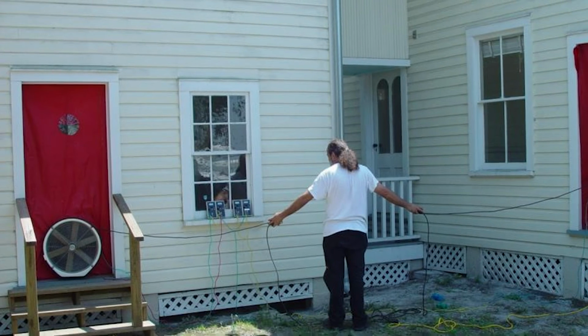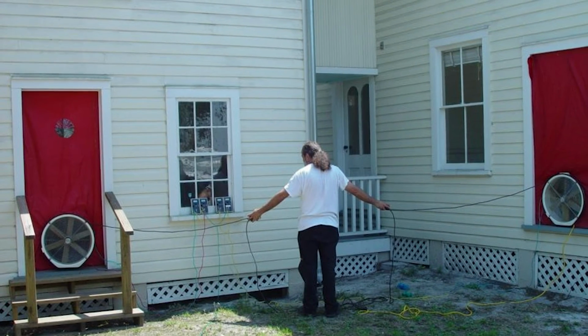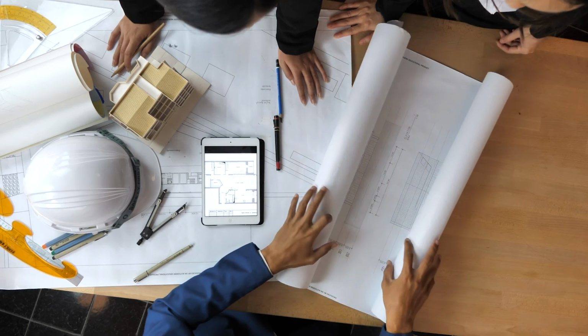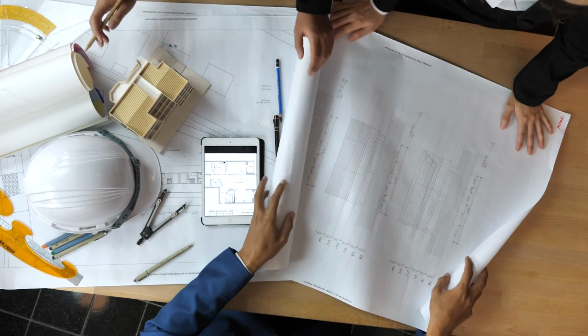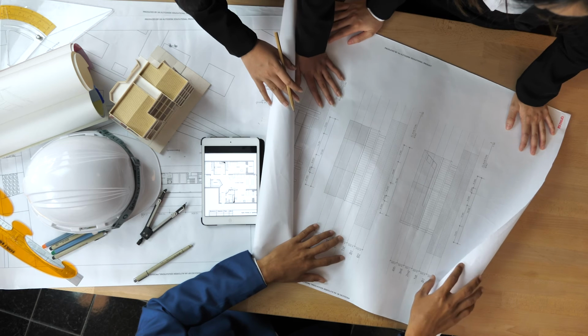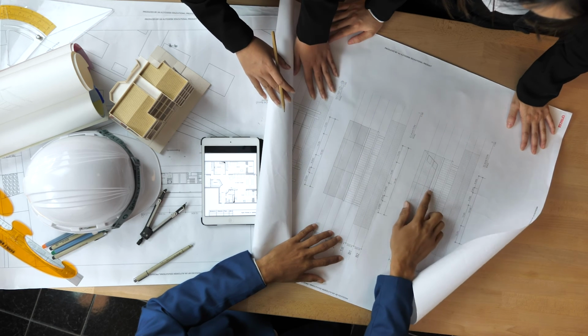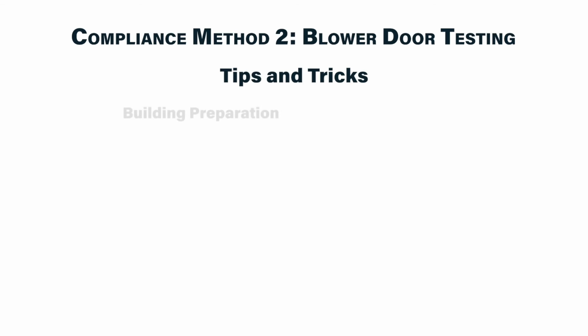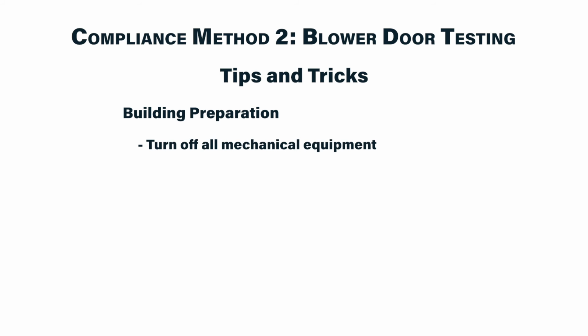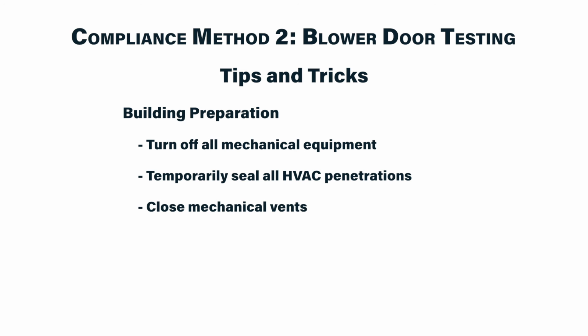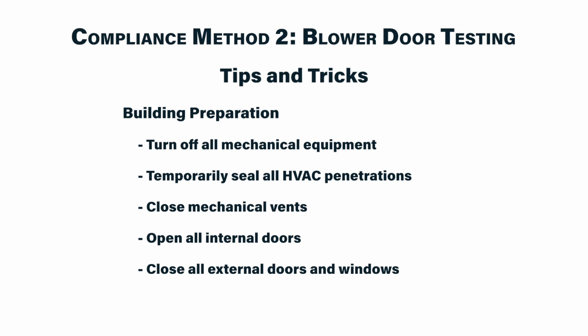First, commercial blower door testing requires multiple blower doors to complete the test. The building layout needs to be reviewed to determine the quantity and location of fans that will create an equal pressure throughout the building. Also, the building needs to be prepared before testing can be done. A few of these preparations include turning off all mechanical equipment, temporarily sealing all HVAC penetrations, closing mechanical vents, opening all internal doors, and closing all external doors and windows.